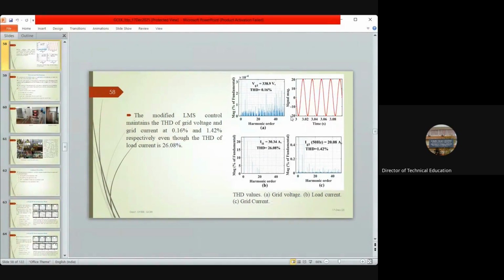Another aspect we demonstrated is harmonics at the local grid side, and how we can reduce them. For example, if you install this device in a commercial area near a hospital, hospital loads produce a lot of harmonics in current. With the same system, we can absorb or compensate for those harmonics and deliver clean, quality power to the grid.